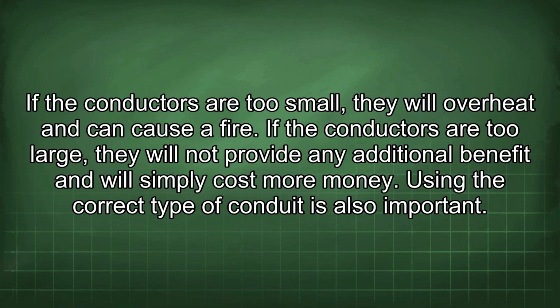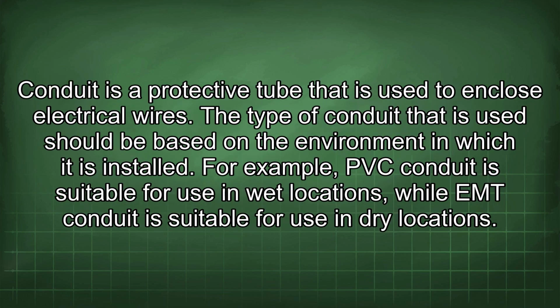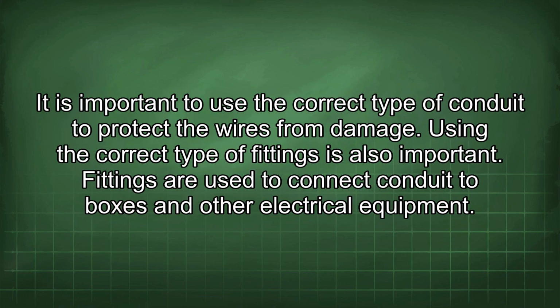Using the correct type of conduit is also important. Conduit is a protective tube that is used to enclose electrical wires. The type of conduit that is used should be based on the environment in which it is installed. For example, PVC conduit is suitable for use in wet locations, while EMT conduit is suitable for use in dry locations. It is important to use the correct type of conduit to protect the wires from damage.